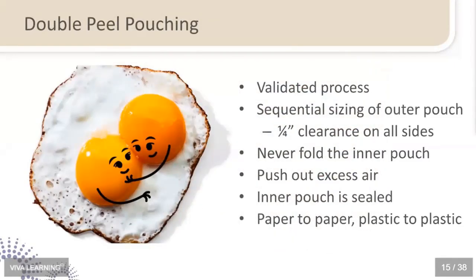Some of you who are involved in community health centers may be following a protocol along with your medical side that advocates for double peel pouching, which essentially means a pouch within a pouch. First of all, you need to make sure that the particular brand of pouch that you're using has been validated to be double pouched. Not all pouches are. You also have to make sure that the instruments have been validated for that process. So it's checking with both manufacturers.